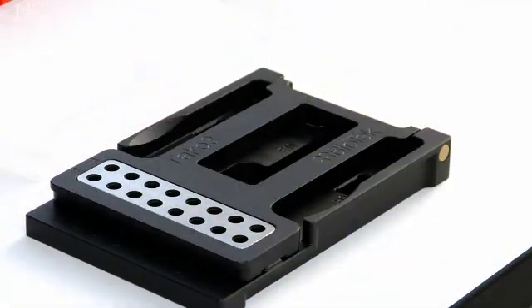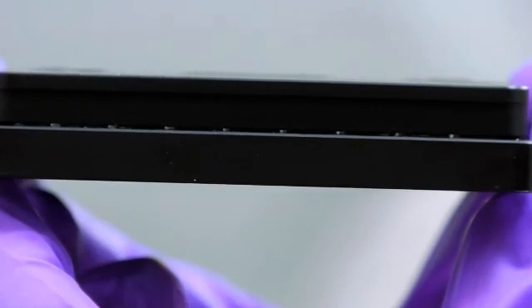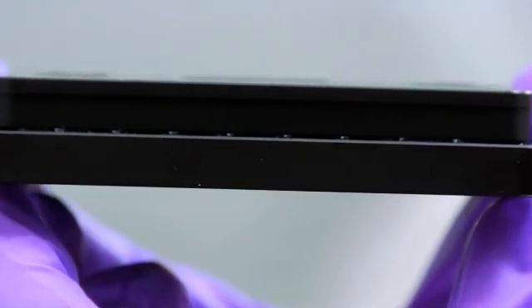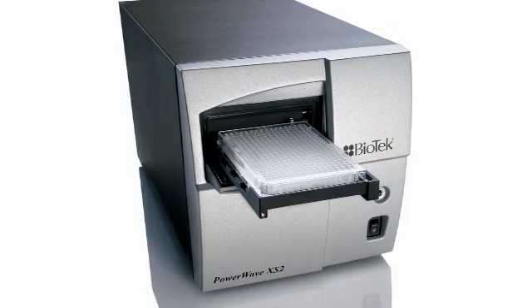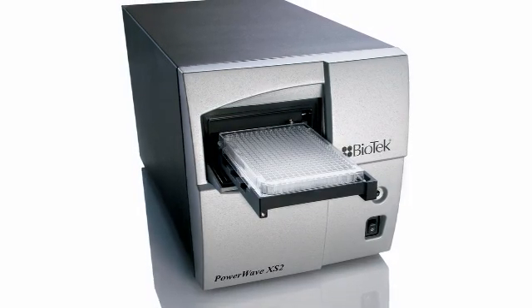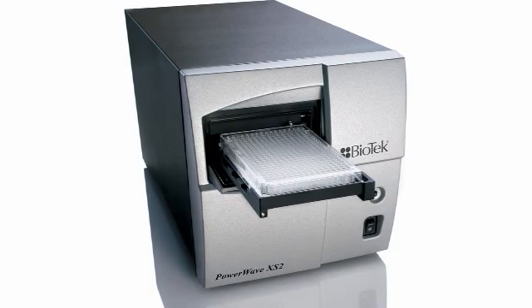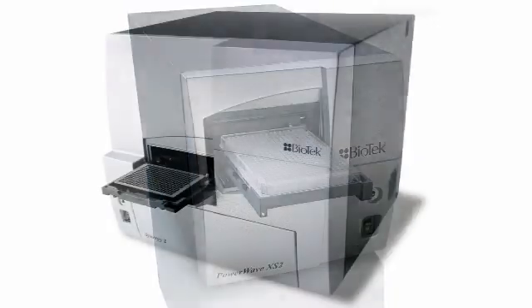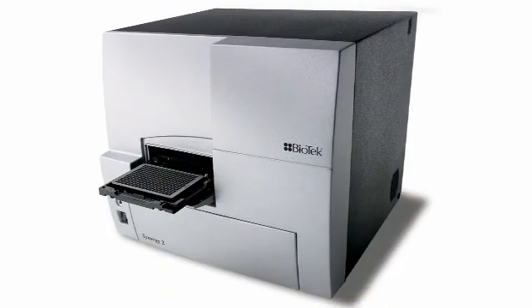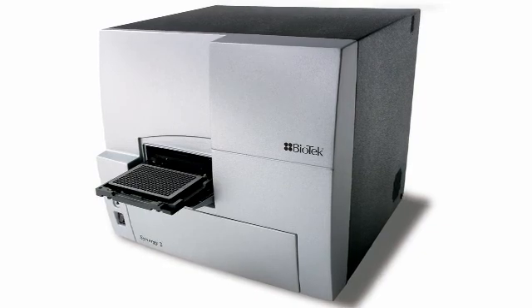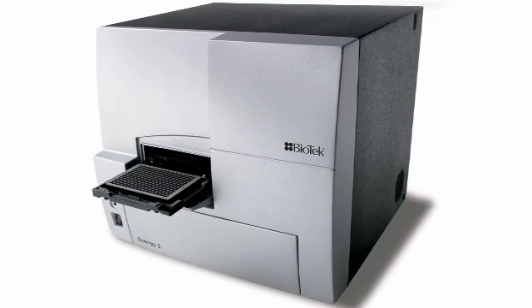When the lid of the Take 3 is closed, the samples are sandwiched between top and bottom slides, held to a nominal 0.5 millimeter path length for each microspot. The absorbance of the samples in the Take 3 plate can be measured using any Biotek microplate spectrophotometer. The fixed path lengths of the plate allow rapid calculation of concentrations based on a standard 1 centimeter path length.